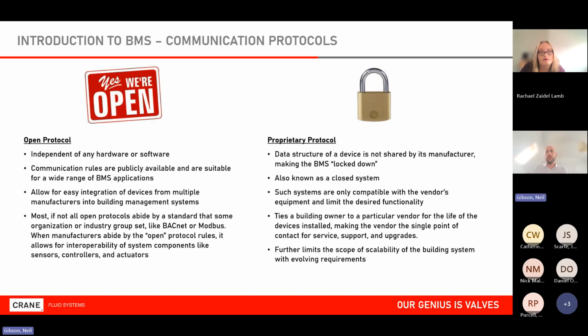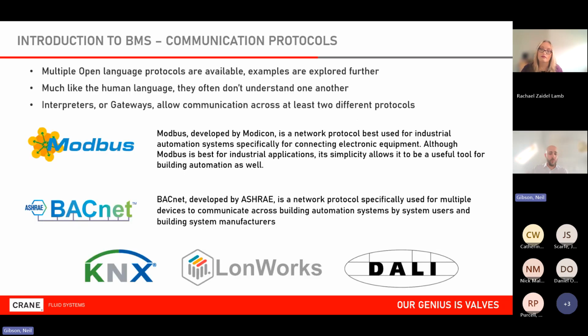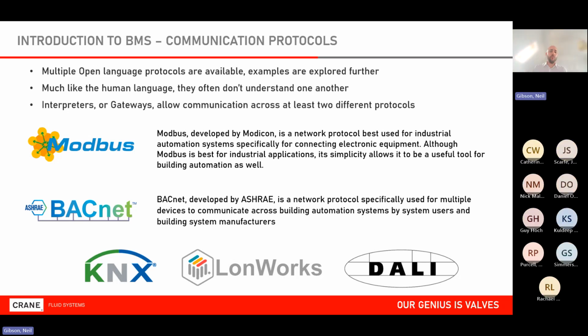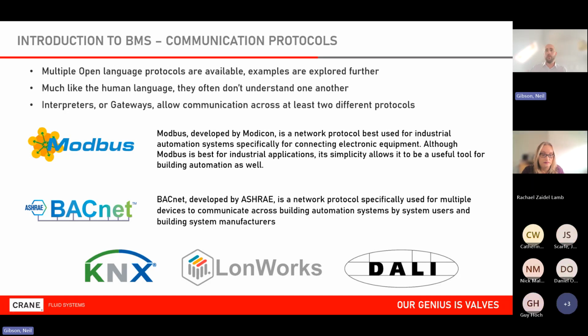Again, you'll know all about this, but we've got two key types of protocol, open and proprietary. The vast majority of manufacturers now use open protocols. Why? Otherwise, we lock the system down. If for whatever reason that manufacturer was to disappear, then it's very, very challenging to integrate new technology into there. So we're all using open protocol, by which I mean the likes of Modbus and BACnet. Again, there are differences around this. I'm not here to sell the benefits of one over the other. What we do see is that our technology uses both. So we look at both Modbus and BACnet. Some other examples there as well.